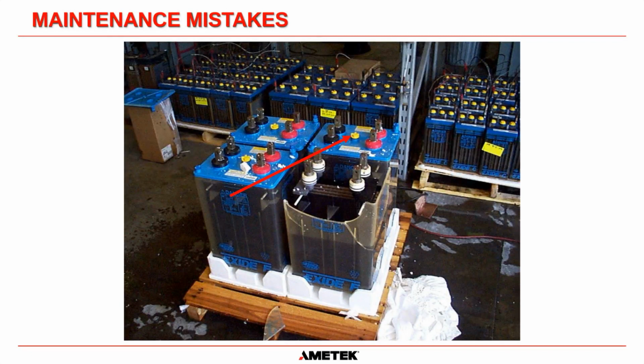And then what happened was, after the recharge or during the recharge, one of their technicians was using this rag down here to wipe down the tops of the batteries, probably to remove most of that polystyrene that's on top of the batteries. And in doing so, he caused an electrostatic charge to build up when he was rubbing the side of these batteries.